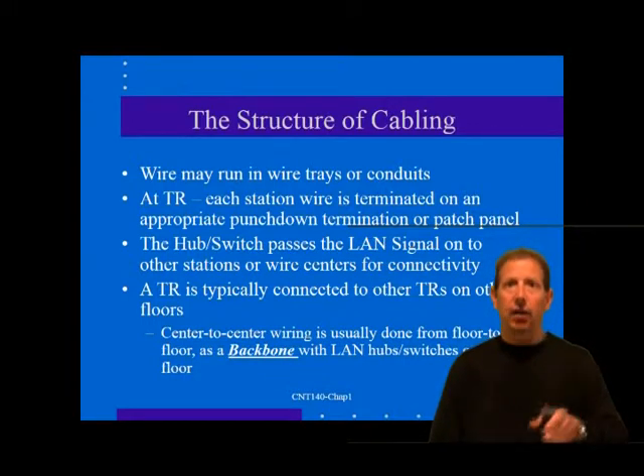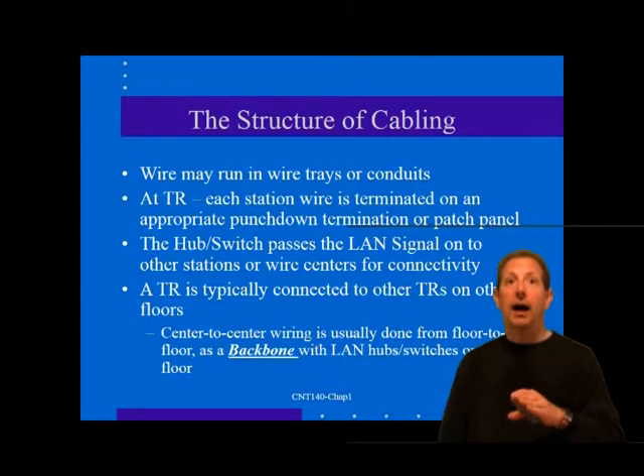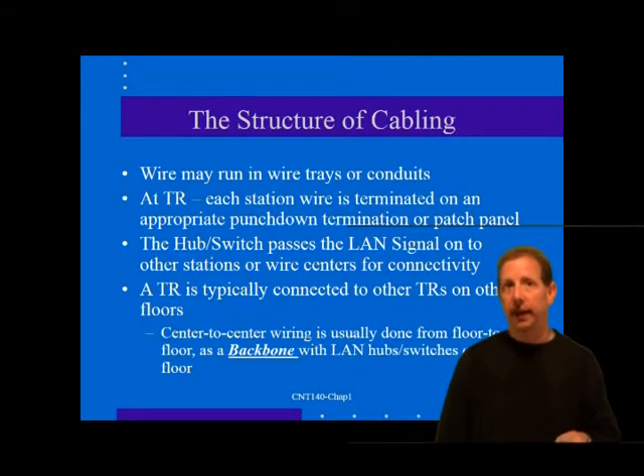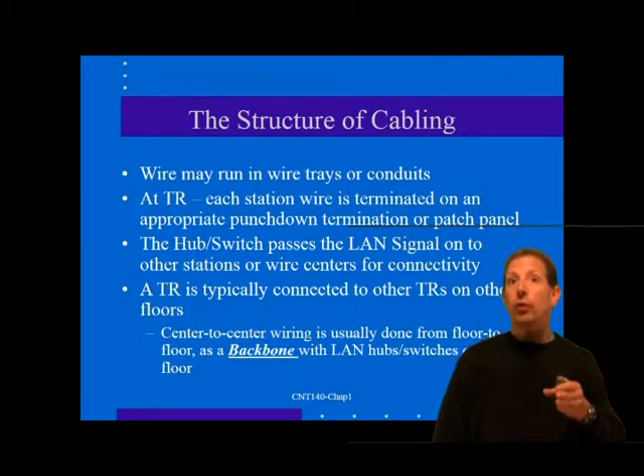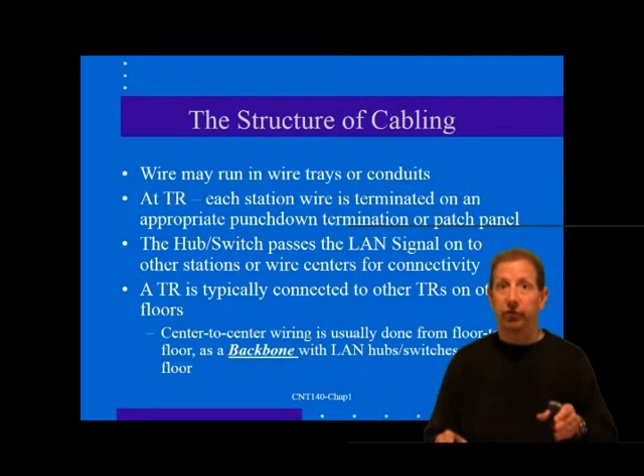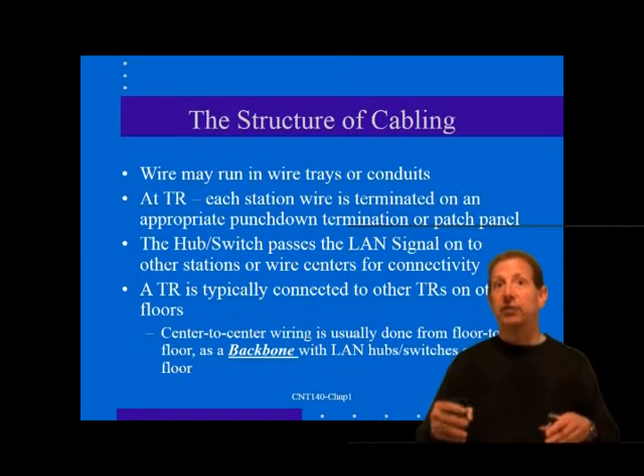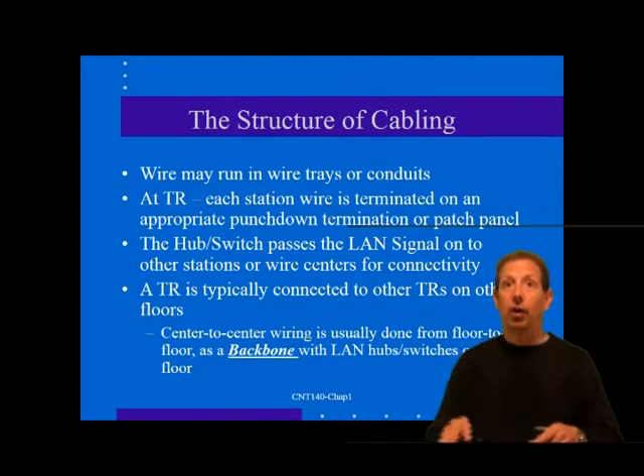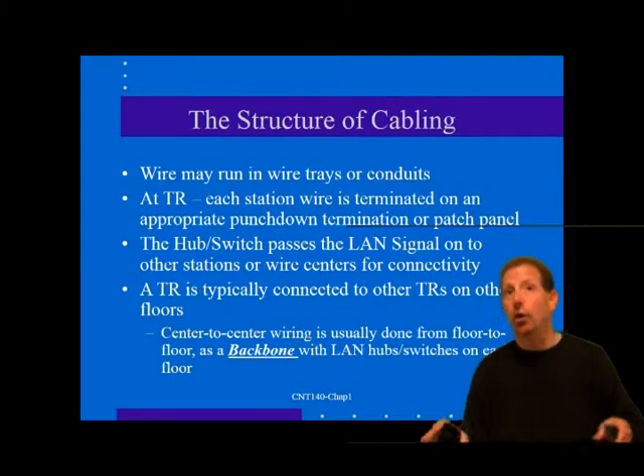Typically a multi-story building model is used to illustrate the structured cabling concept. On each floor, a telecommunications room (TR) concentrates all station cables for that floor. Each workstation location has a wall or surface-mounted jack, and the network cable runs directly to the wire center — this is called a home run. The wire may run in wire trays, conduit, or over supports using J-hooks on the floor joists above drop ceilings.